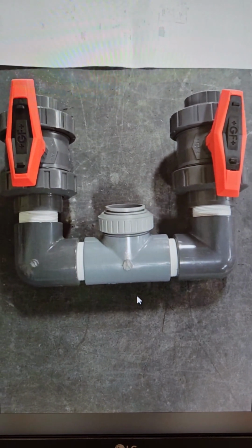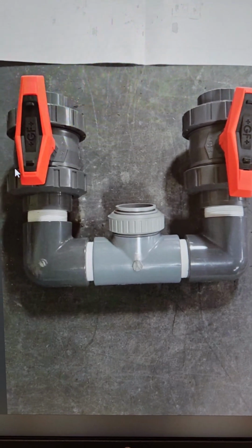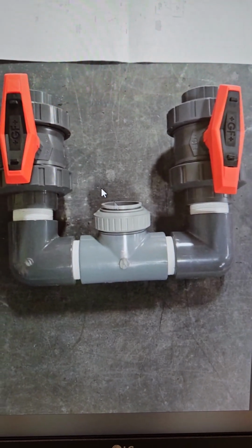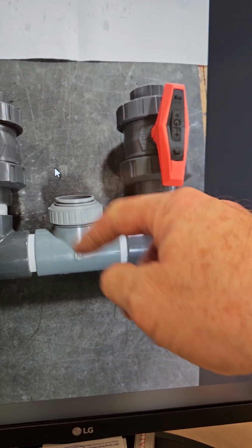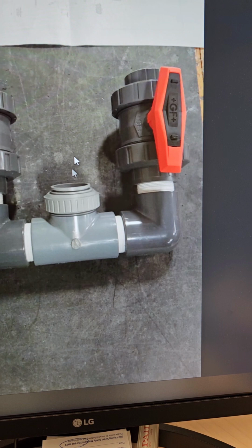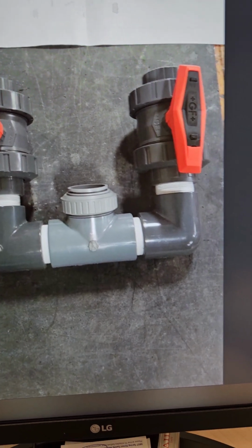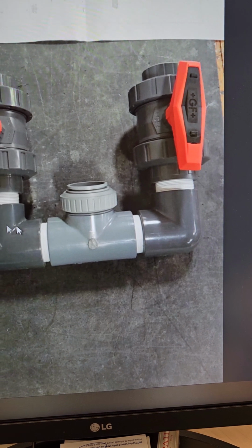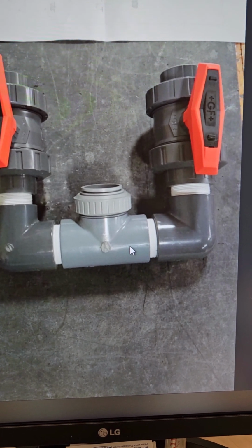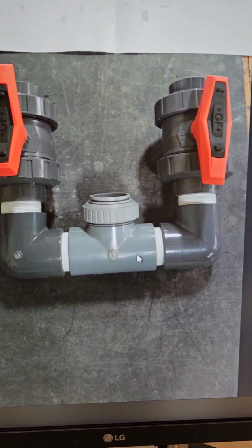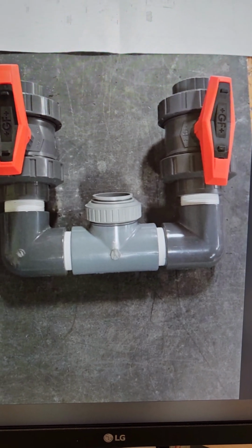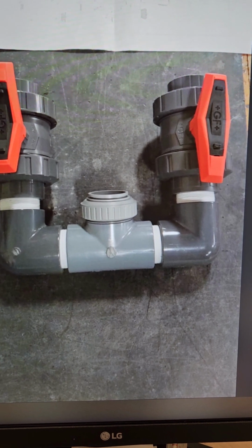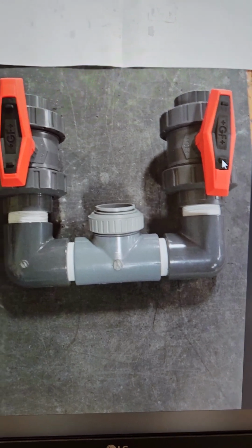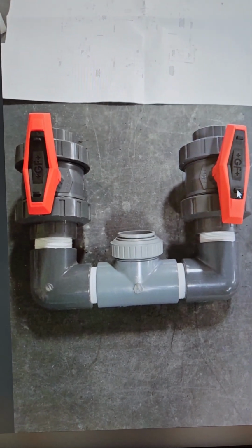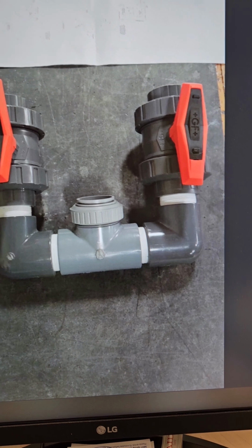This is how we build a union trap. I like to put a drain on the bottom of the valve, so that when you isolate this valve and take a probe out of the water, the way this union trap works is you unscrew that and pull the probe out. It can cause a lot of buildup pressure because you're extracting a probe that's submerged in water and there's no air to get in to displace the probe that's coming out of the liquid. Since this trap is made to keep it wet, no matter what you do, when you shut off both of these, this ends up being flooded because the pipes extend up farther and there's liquid there, so all the air goes out and you have a completely flooded area there, and they don't want to unscrew.